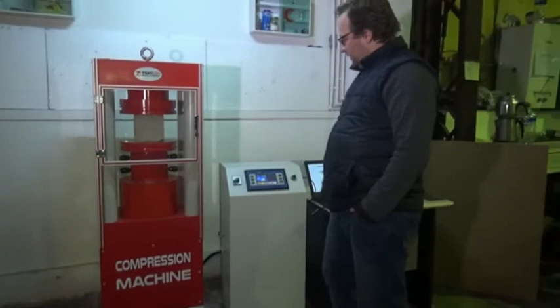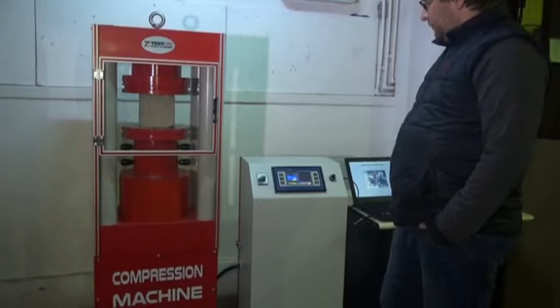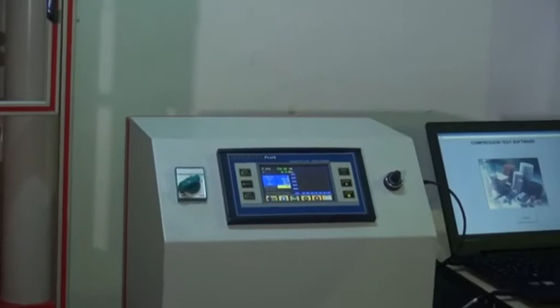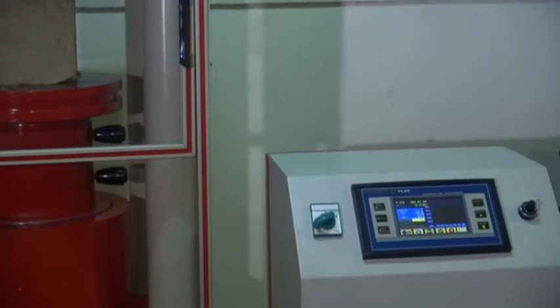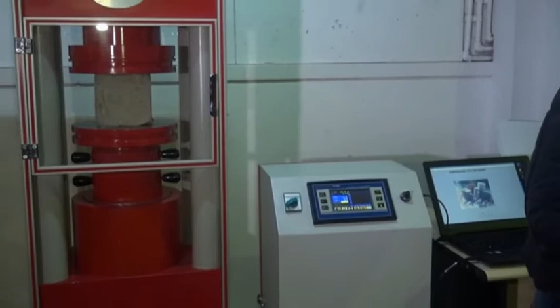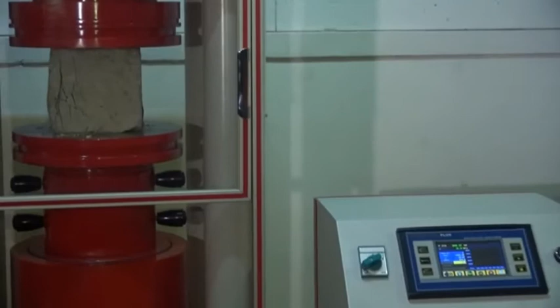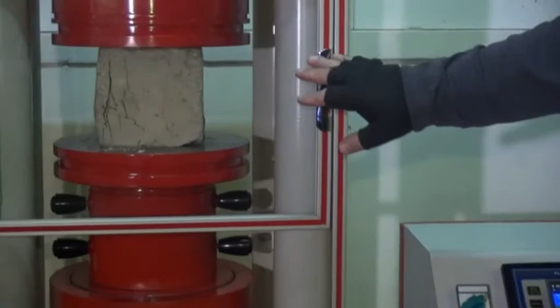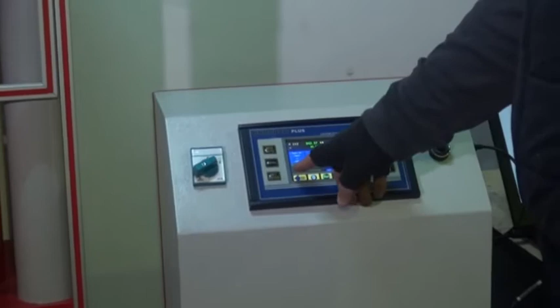And at the same time we will see the graphic and the testing load. Now it's loading. Also the sample starts to break, and we will see some cracks on the sample. Yes, it's almost finished, and the system automatically recognized this sample is broken because the test load is going down after break detected, and automatically stops the test.